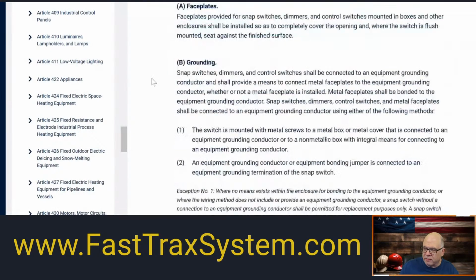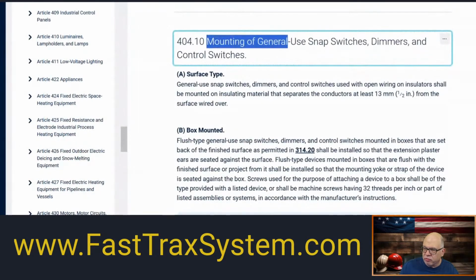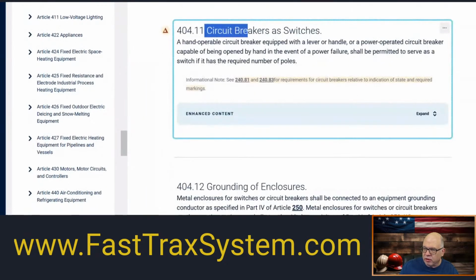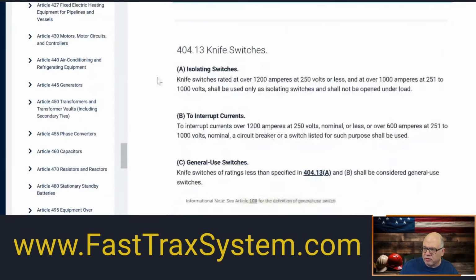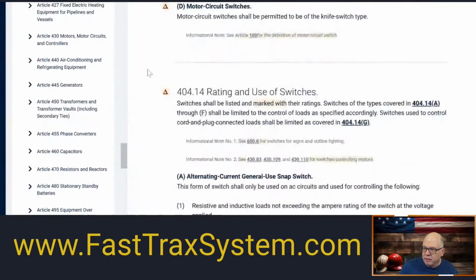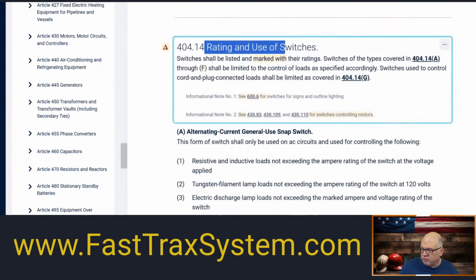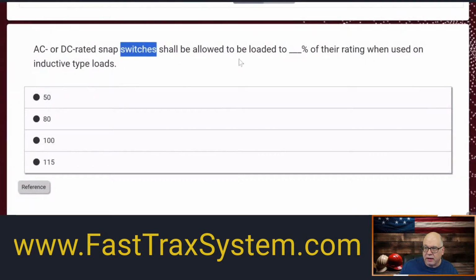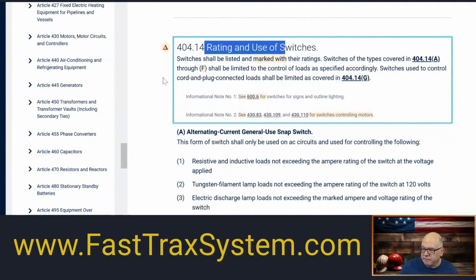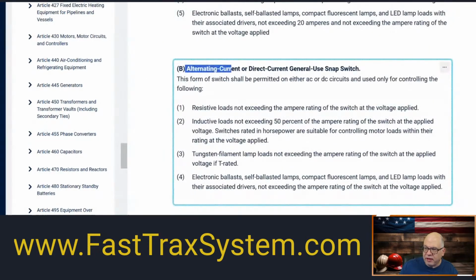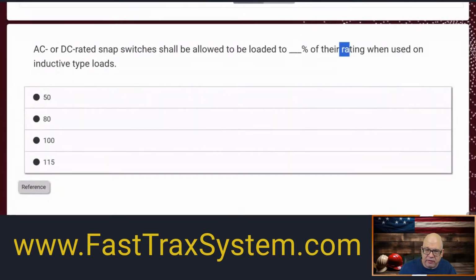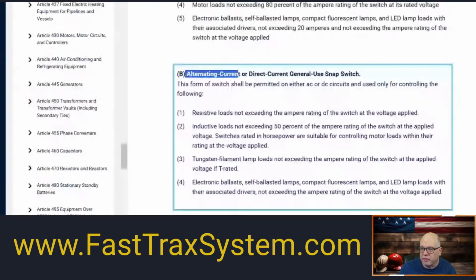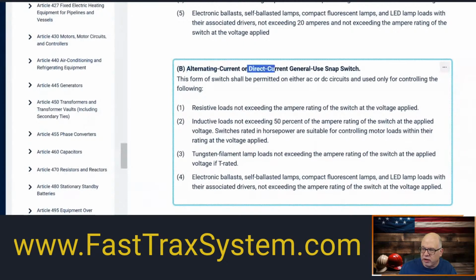General use snap switches, okay. Mounting of general use snap switches, okay. Circuit breakers as switches, okay. Grouping of switches, knife switches, ratings and use of snap switches. Because remember what it said in our question: what is the rating of that snap switch when it's used with an inductive type load? All right, so we're going to be looking here. And AC, alternating current. This may throw you because the question didn't write it out. The question just had it as AC, so always be aware of that. So alternating current or direct current, general use snap switches.